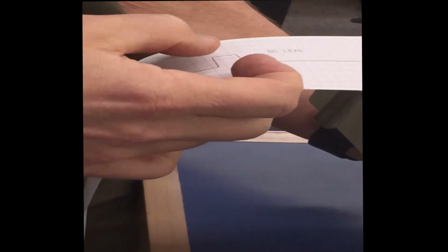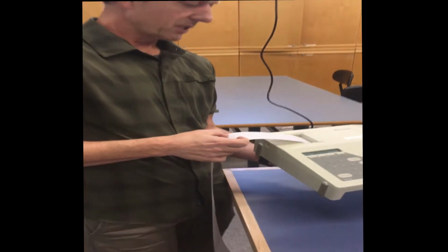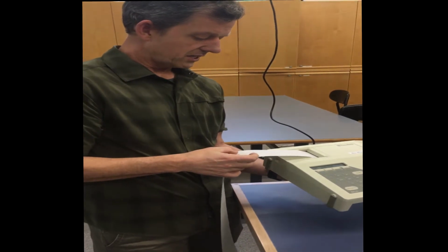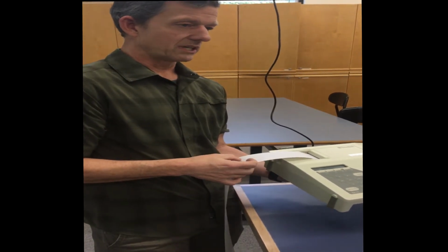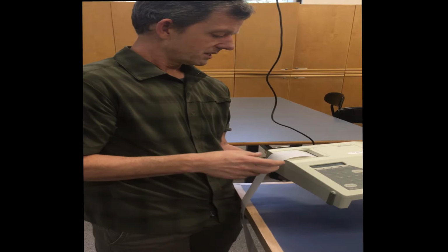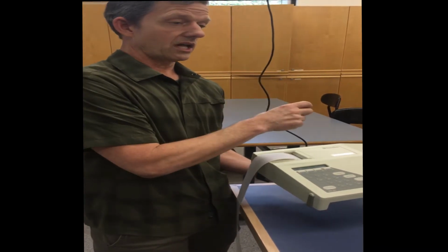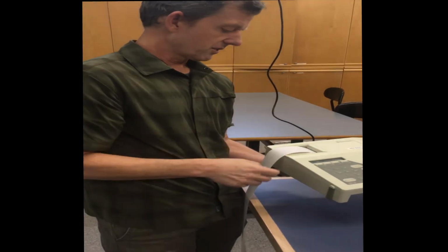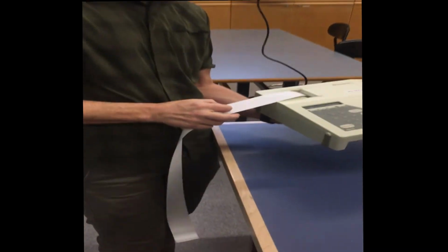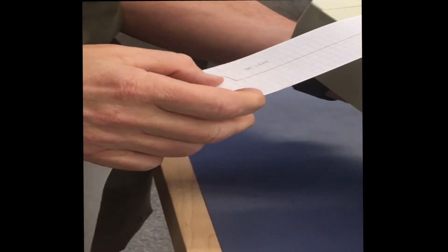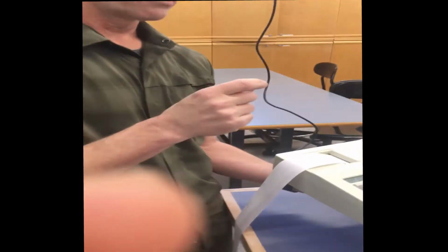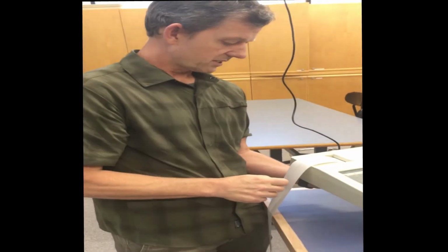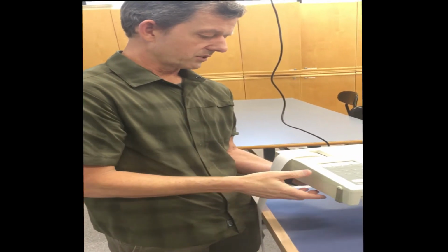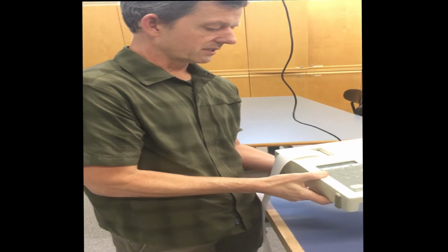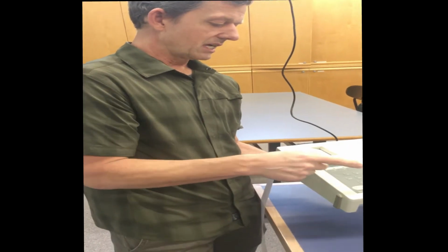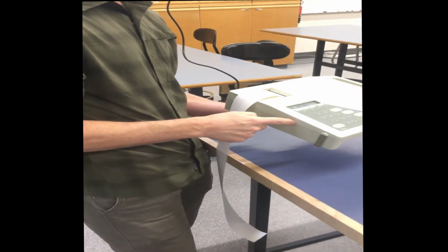So it's important to have a calibration signal, and typically if you're working with a subject or a patient, you're going to do a calibration signal at the beginning of the experiment or of the testing, and you're also going to do a calibration signal at the end just to make sure that it hasn't changed. So again, the purpose of that is that you could measure that distance and say this is what 1 millivolt is. So when you're measuring your QRS complexes, you can look at that and determine what the amplitude of your QRS complexes is. So do a millivolt at the beginning and do a millivolt calibration signal at the end.